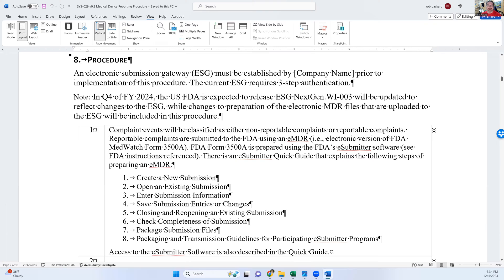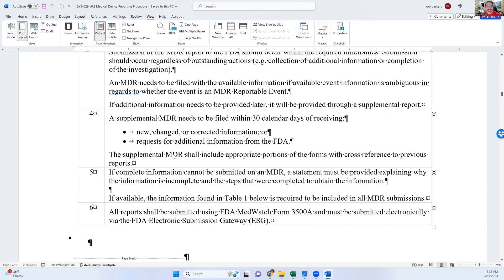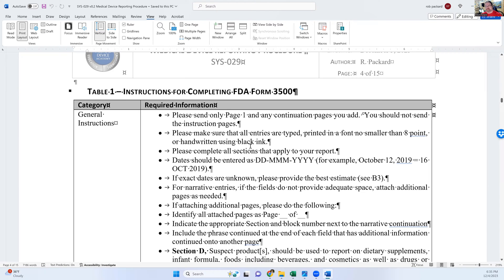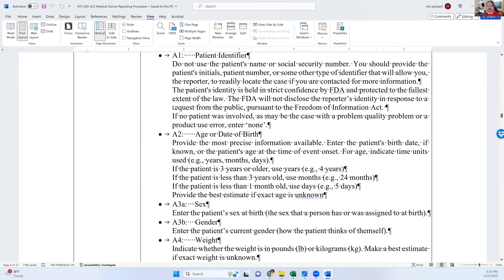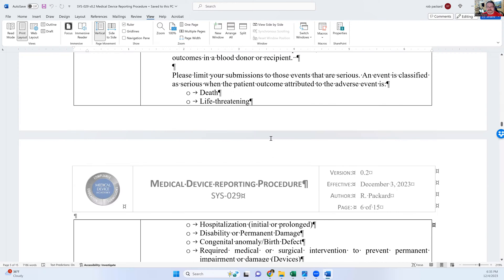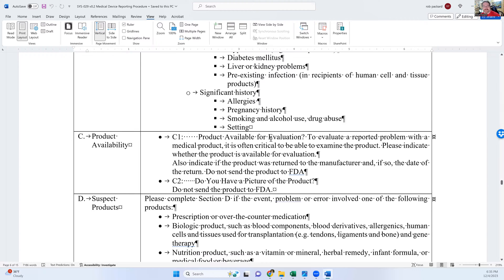One of the things we added is a note about the change for release one of ESG next-gen, and I state that the ESG procedure is not included here — you have to look at work instruction three for that. Then you get down to Table 1: instructions for completing FDA Form 3500A. Form 3500 is the abbreviated version used by hospitals; Form 3500A is the one manufacturers use. We put everything in here, including the instructions on how to answer each field, so the guidance is included in the procedure. We went from a five-page document to a fifteen-page document.